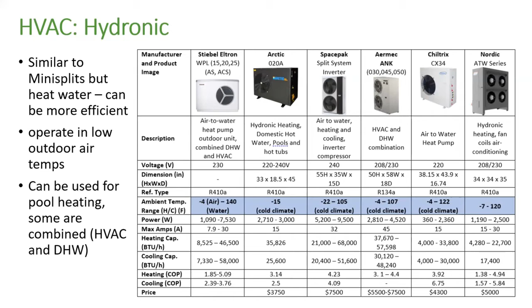These are all examples of air-to-water heat pumps, and most of them operate up to 130 to 150 Fahrenheit, but that can be too low for radiators. If you replace your radiators, there are ones by Jaga, J-A-G-A, made for low temperatures down to 110 Fahrenheit, so you can definitely use any of these heat pumps with a hydronic system. The question is whether you get a really high temperature one so you can reach 160 Fahrenheit, and those are very limited. Usually you'd go to 150 and then use electric resistance for the last 10 degrees, which isn't efficient, but that's what you do. Or replace your radiators while doing this work, so you get the same comfort in the exact same place in your residence during the retrofit. The radiators are in the same space, but it works for electrification. So those are your two answers.